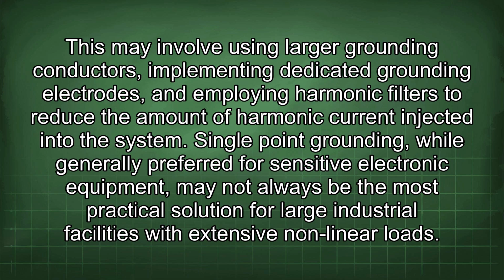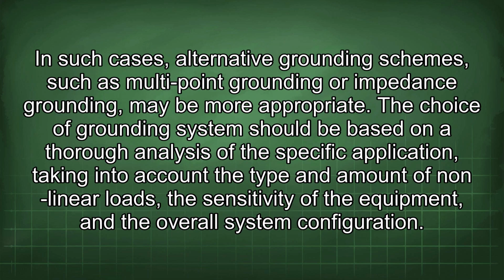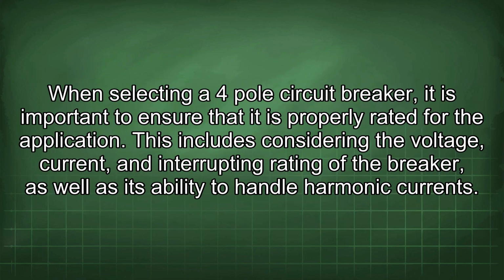Single-point grounding, while generally preferred for sensitive electronic equipment, may not always be the most practical solution for large industrial facilities with extensive nonlinear loads. In such cases, alternative grounding schemes such as multi-point grounding or impedance grounding may be more appropriate. The choice of grounding system should be based on a thorough analysis of the specific application, taking into account the type and amount of nonlinear loads, the sensitivity of the equipment, and the overall system configuration. When selecting a 4-pole circuit breaker, it is important to ensure that it is properly rated for the application.